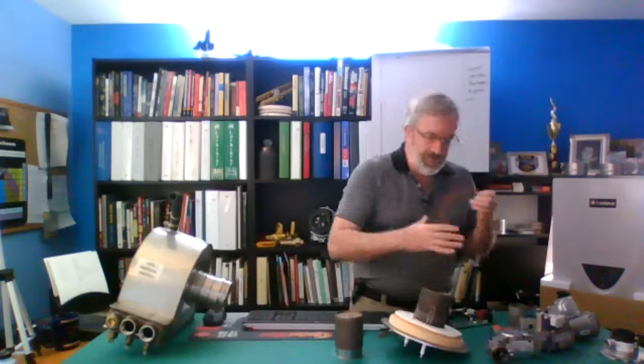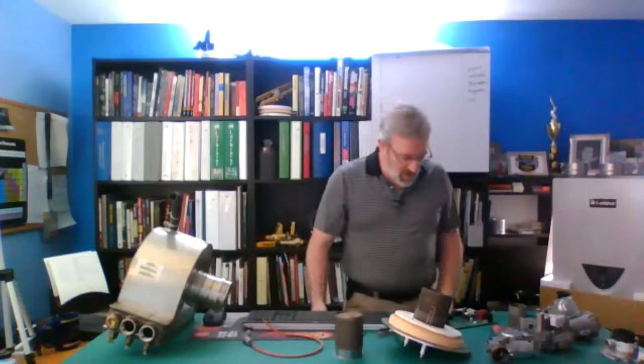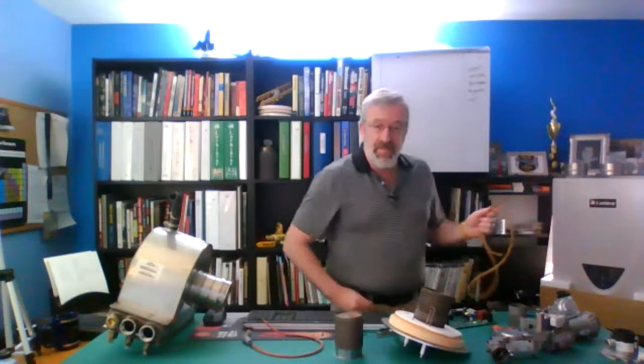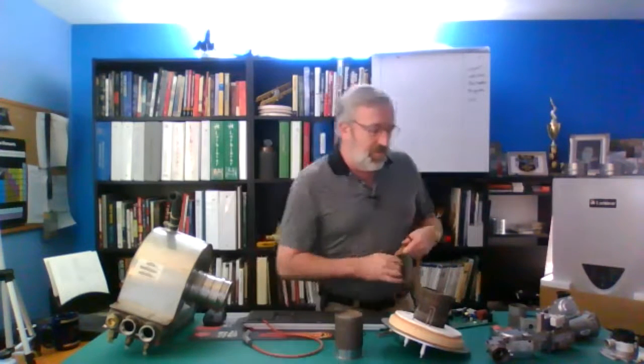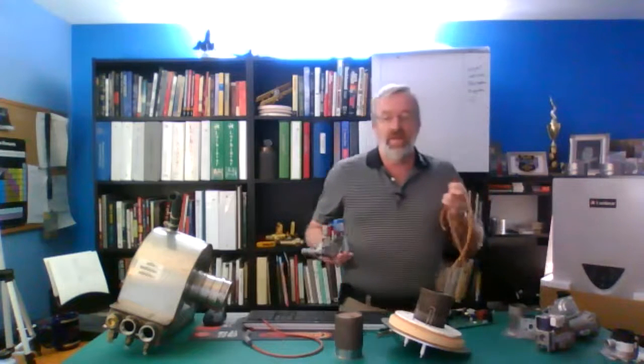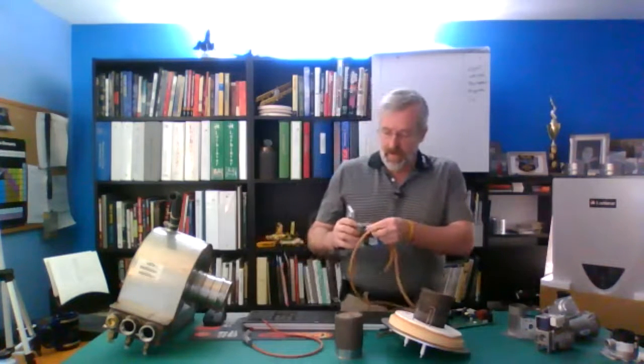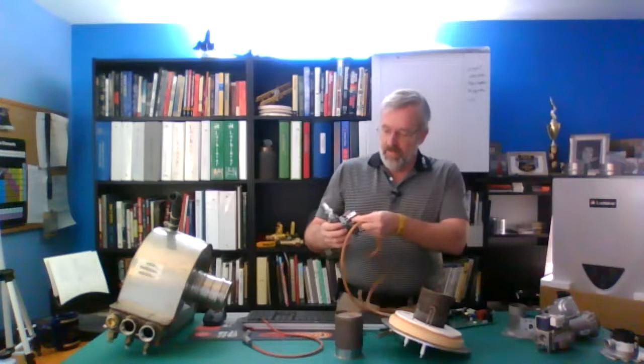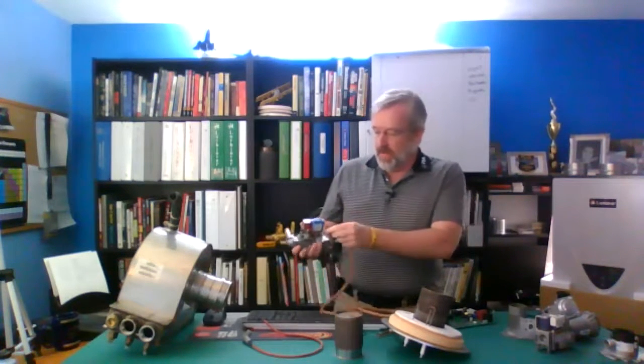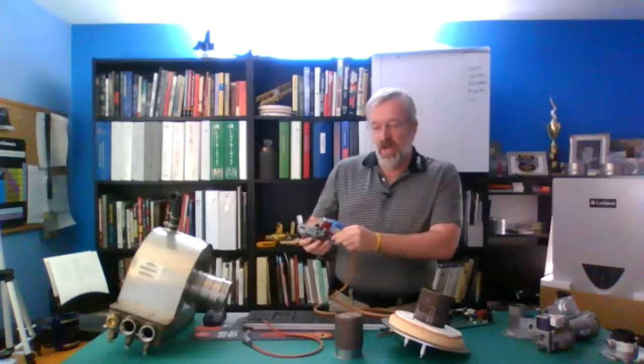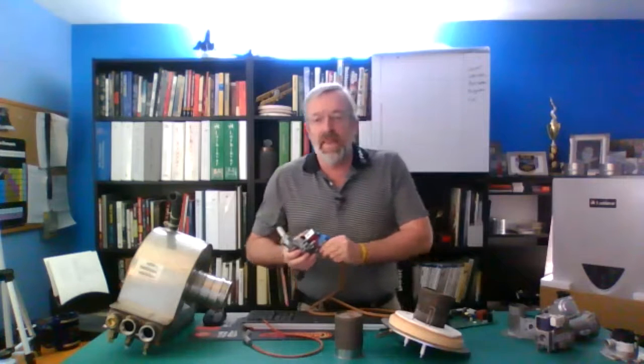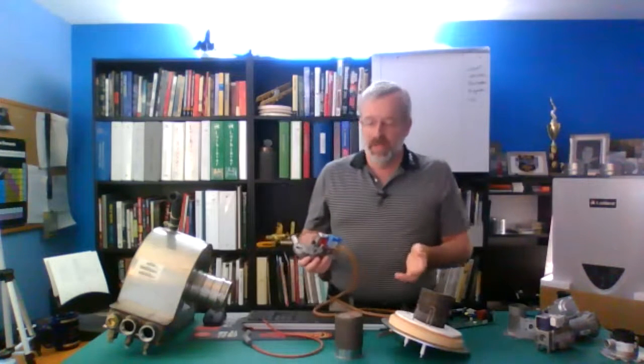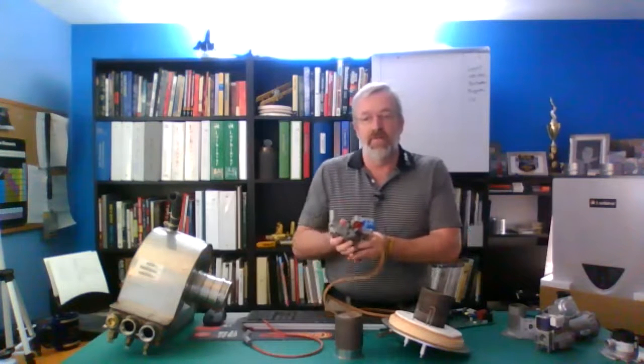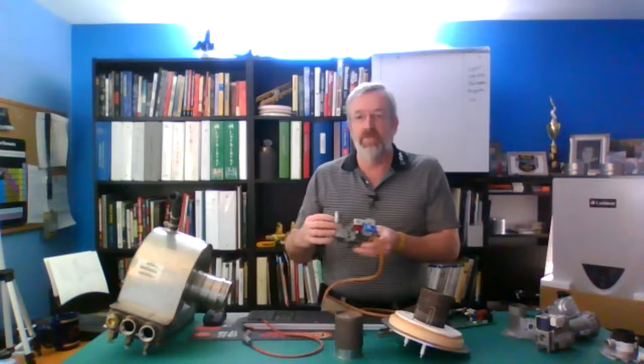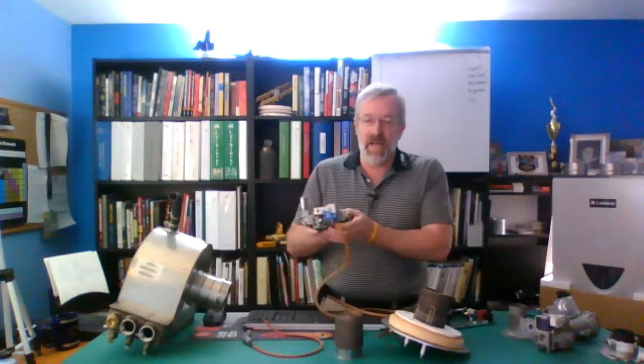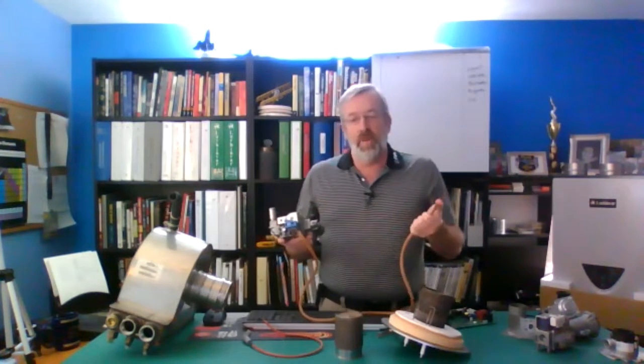So line my stuff up. What we want to do is make sure we got the triangle of combustion there: air, fuel, spark. So generally my recommendation, if I've got a boiler that's not firing, I want to put my test hose on the inlet side of that gas valve. Now, why the inlet side? The inlet side is positive pressure. The outlet side is negative pressure because we're creating a negative and pulling the gas through there. So when I'm on the positive side of it here, I'm going to connect my hose to my manometer.